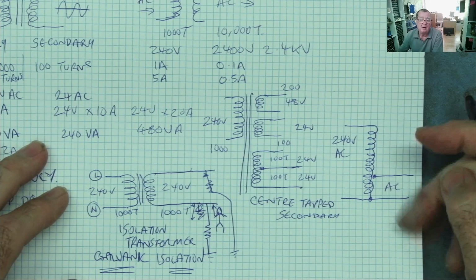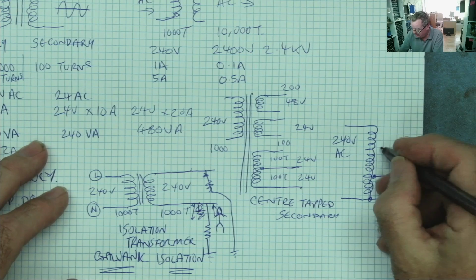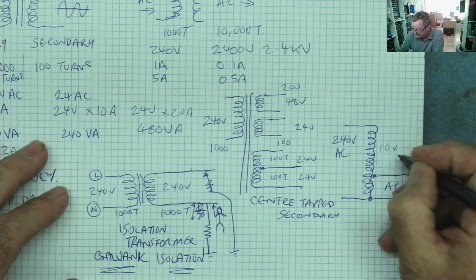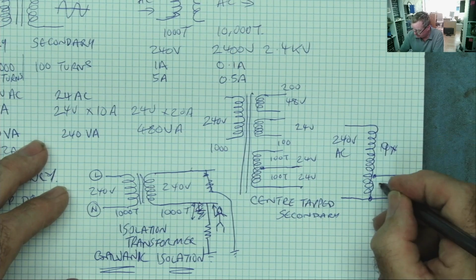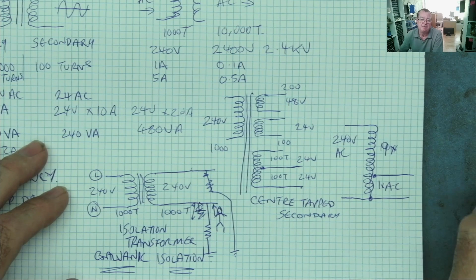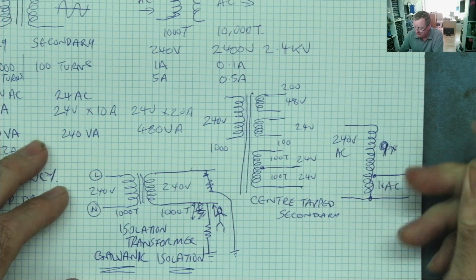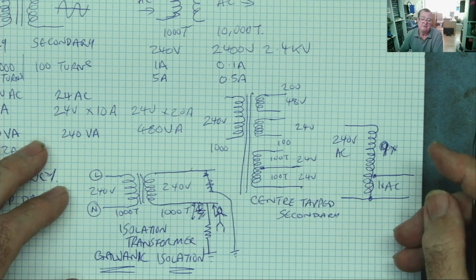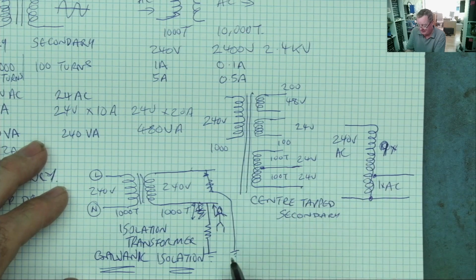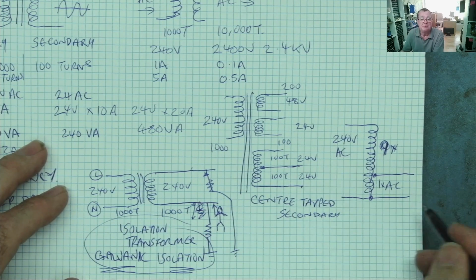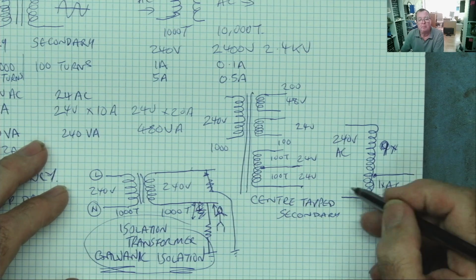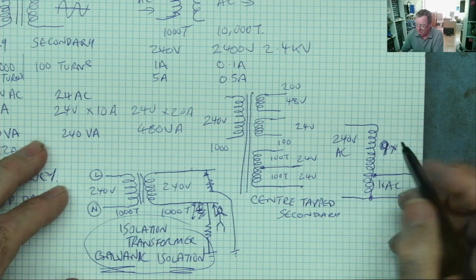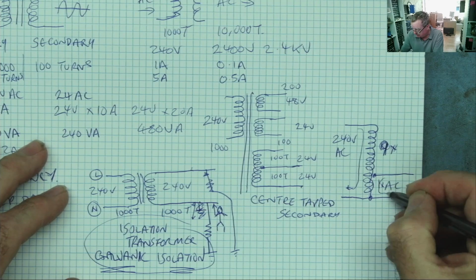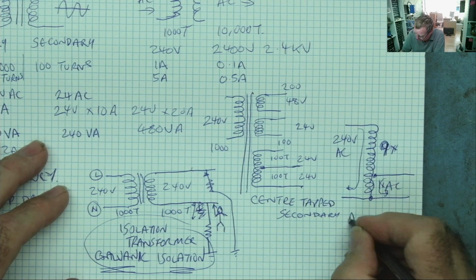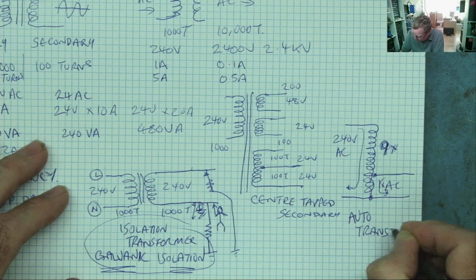Depending on where you put the wire tap, and the same applies, the ratio of turns - so if there are 9 times as many turns here to the one there, 1 times to 9 times, you'll get 1/10 of the voltage coming out here. So it's the ratio of turns. This is also dropping down the voltage, but it's not giving you any isolation from the mains, and it's not allowing you to draw more current than you've got flowing through that, because only one current flows through all of it, that way or that way. This is called an autotransformer.